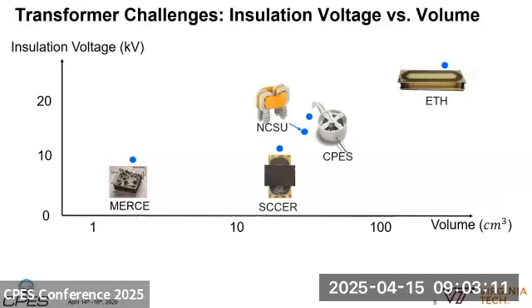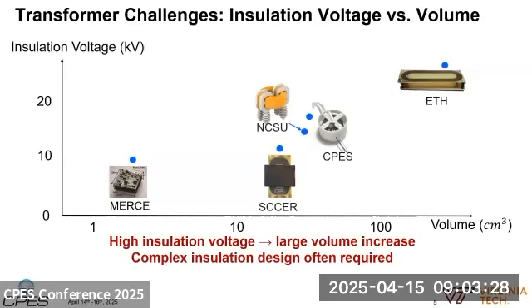Another transformer challenge is insulation design. There are many insulation designs to increase the insulation voltage, but in general, as you increase the insulation voltage requirement, your overall size becomes much larger, and complex insulation design is often required.